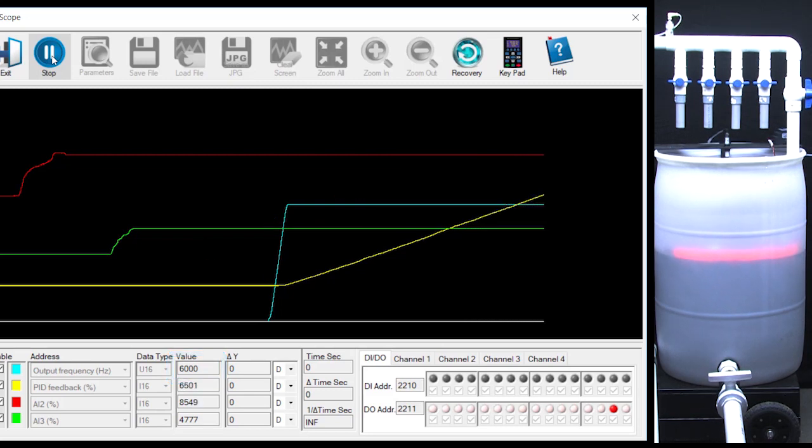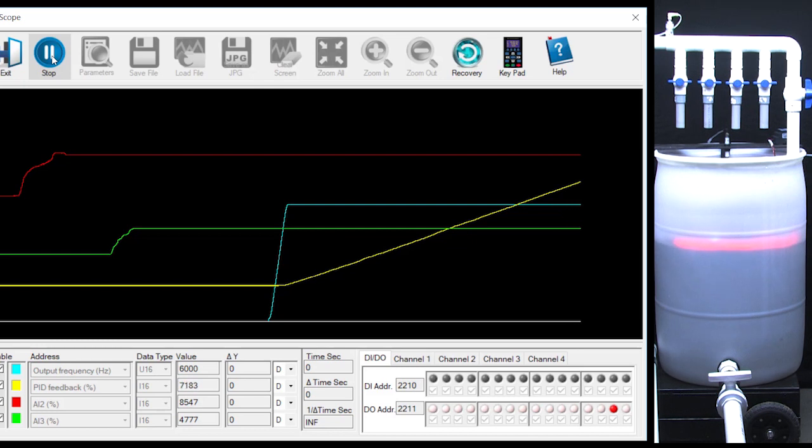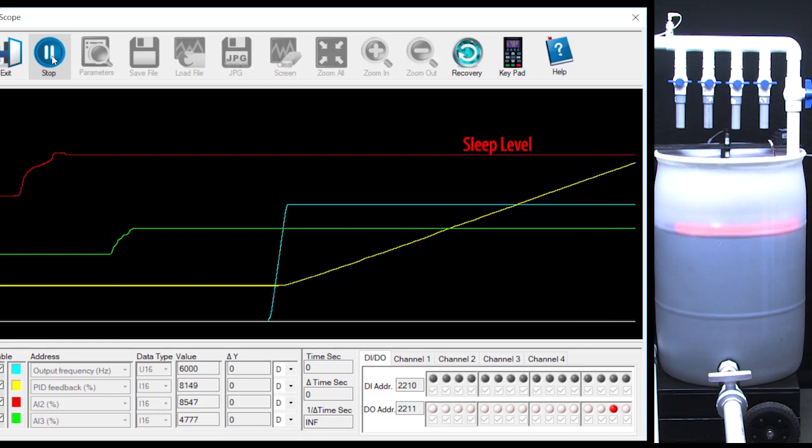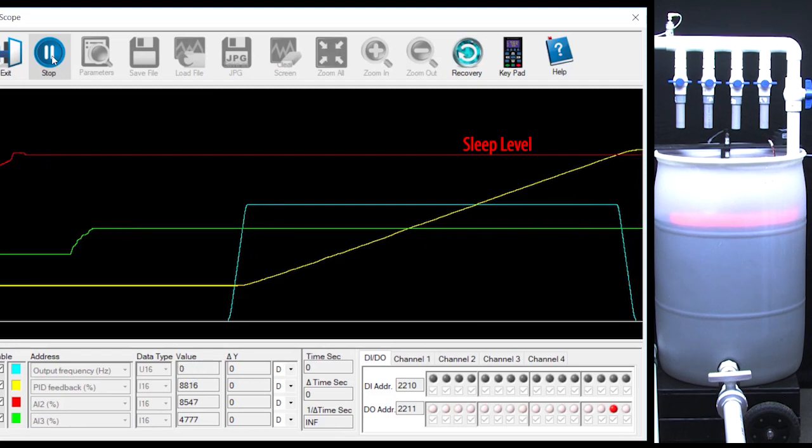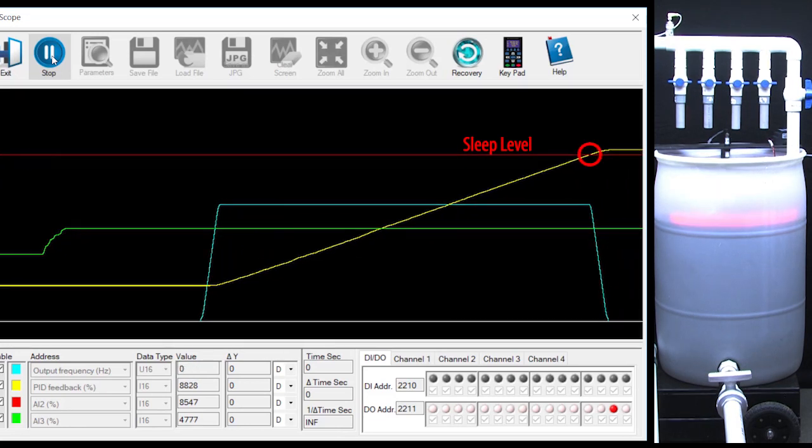But before PID can reach the 95% set point, the yellow water level or process variable hits the red sleep level and sleep mode disables the drive's output frequency which ramps back to 0 Hz at the deceleration rate we set.